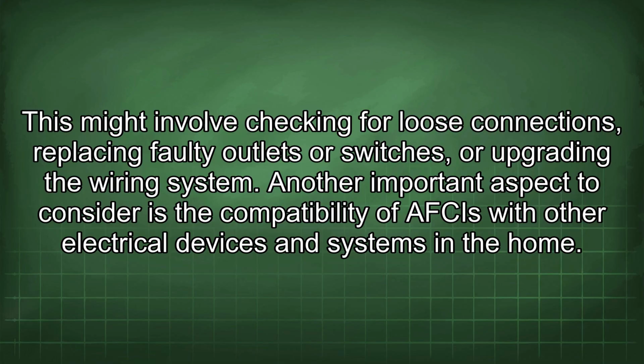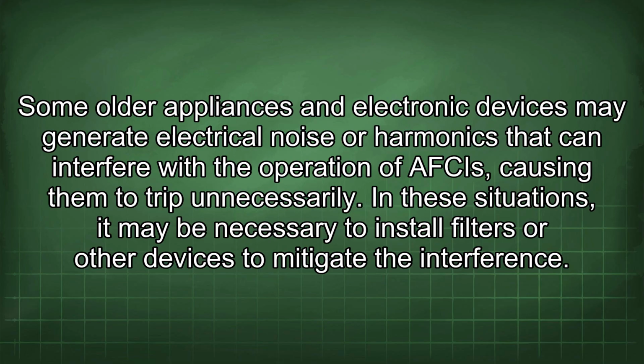Another important aspect to consider is the compatibility of AFCIs with other electrical devices and systems in the home. Some older appliances and electronic devices may generate electrical noise or harmonics that can interfere with the operation of AFCIs, causing them to trip unnecessarily. In these situations, it may be necessary to install filters or other devices to mitigate the interference.